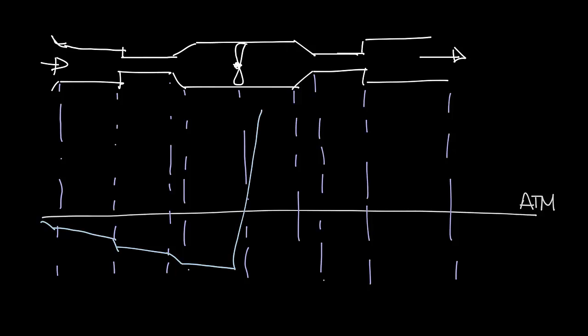Then it gets to the fan and the fan boosts the pressure up here to above atmospheric pressure. Finishes the ductwork. Again there's a little bit of loss. A loss of the transition. A little more straight duct. It hits this pretty hard expansion. There's more pressure loss. It goes out and then it hits the space. It will return to atmospheric pressure somewhere after the end of, we'll say, the diffuser, which I didn't draw in.